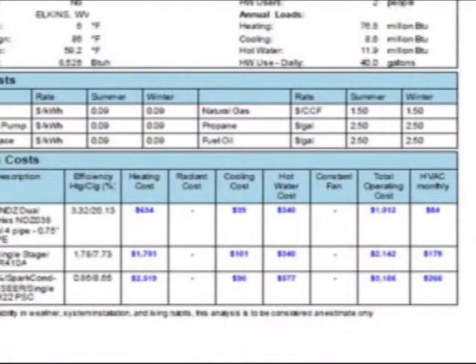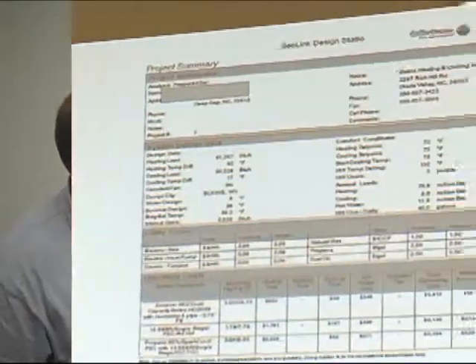They're getting the tax credit and it helps with the hot water. This line here gives me a heating cost for my geothermal unit — that's $634 annual heating cost. And then I've got a 13-SEER air source heat pump at $1,701. And then a 90% efficient propane furnace at $2,519. But you get a total annual heating, cooling, and hot water cost for the geothermal unit on this project — and this is up in DPA, by the way — it's $1,000 annually.